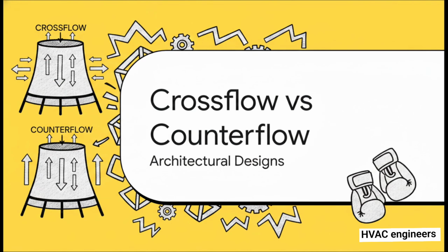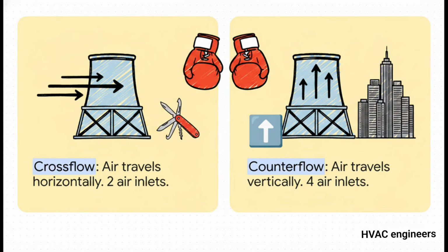Okay, section three, crossflow versus counterflow. It's a bit of a heavyweight bout here. On one side, we've got the crossflow tower, where air travels horizontally across the falling water using just two air inlets. On the other side, the counterflow tower, where air travels straight upward, fighting directly against the falling water, using four air inlets. Now, if you're in a dense urban area and your heat load is under 750 tons, counterflow is going to be your champion because it saves vital footprint space. But as we'll see, crossflow brings some incredible versatility to the table, especially with unpredictable environments and maintenance.